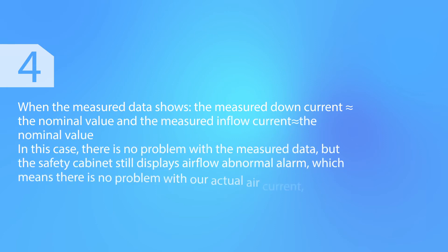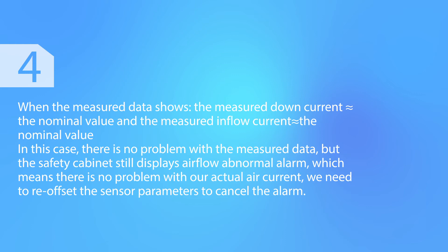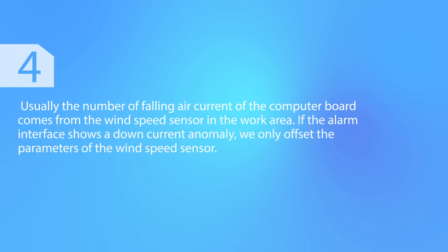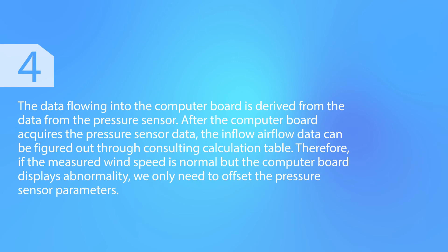When the measured data shows that the measured down current matches the nominal value and the measured inflow current matches the nominal value, there is no problem with the measured data, but the safety cabinet still displays an airflow abnormal alarm. This means there is no problem with our actual air current, and we need to re-offset the sensor parameters to cancel the alarm. The down current reading on the computer board comes from the wind speed sensor in the work area — if the alarm shows a down current anomaly, offset only the wind speed sensor parameters. The inflow data is derived from the pressure sensor; after the computer board acquires the pressure sensor data, the inflow airflow is calculated through a lookup table. Therefore, if the measured wind speed is normal but the computer board displays an abnormality, we only need to offset the pressure sensor parameters.